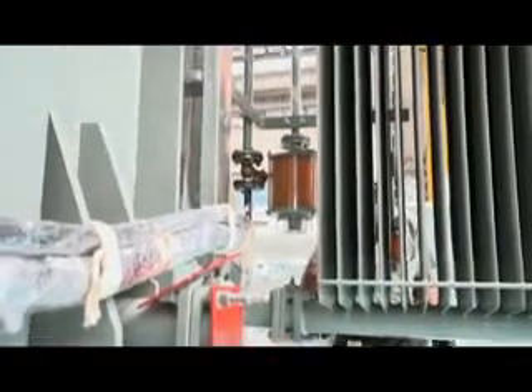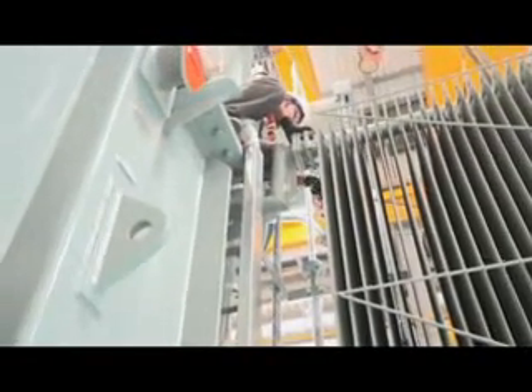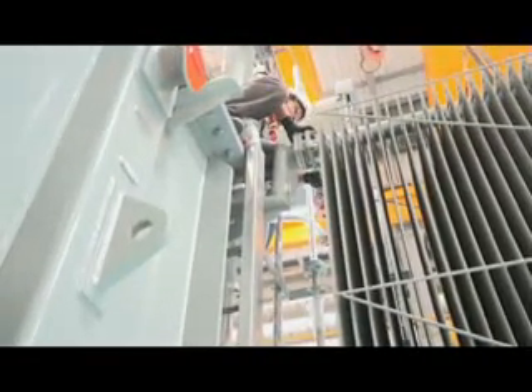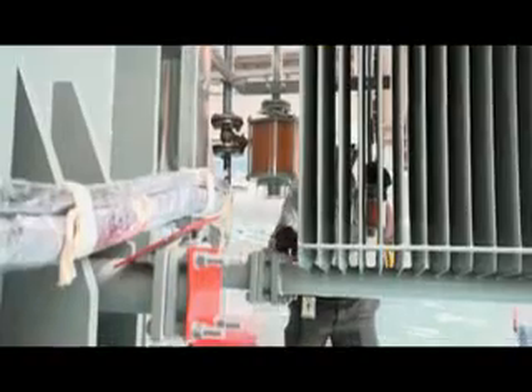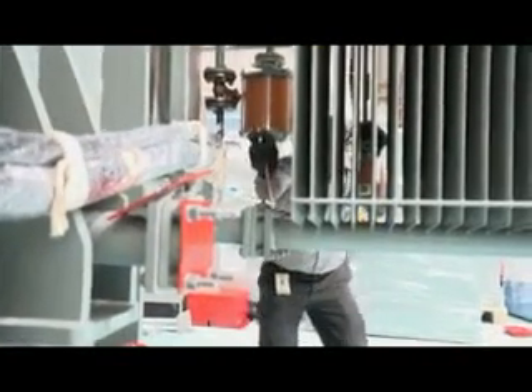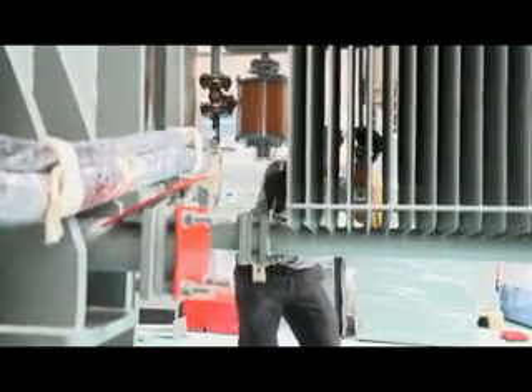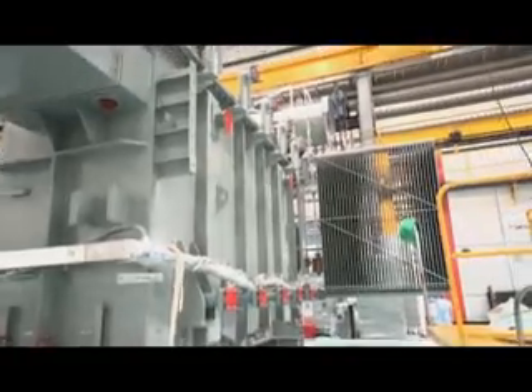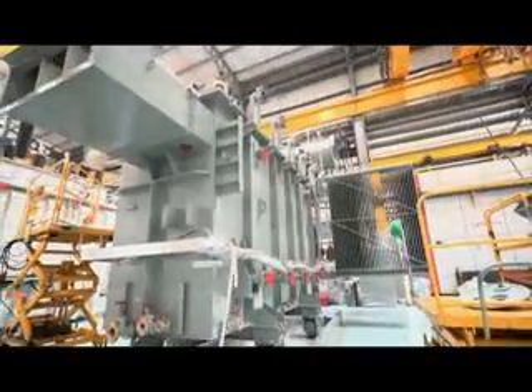Dissipation of heat in the transformer radiator can be accelerated further by forced air provided by means of fans. These fans are fitted either on the radiator bank itself or nearby the bank, but all the fans must be faced towards the radiator. Sometimes the cooling rate of convectional circulation of oil is not sufficient. At that time, an oil pump may be used for speeding up oil circulation.